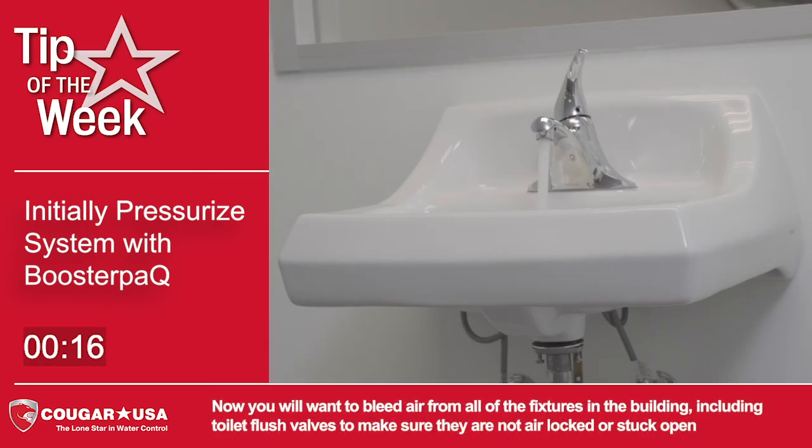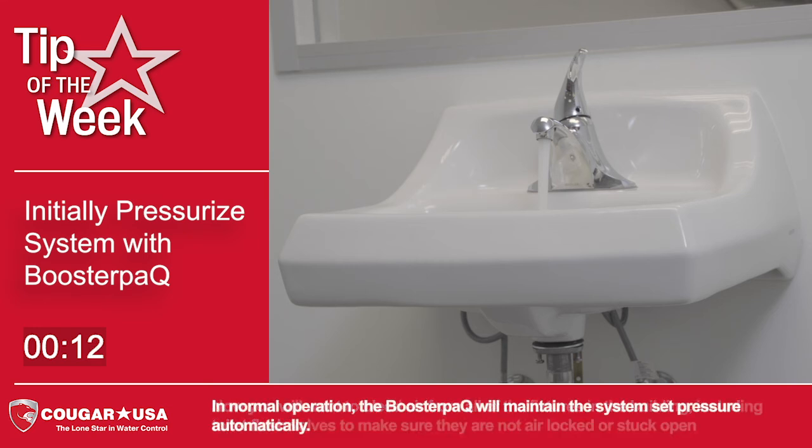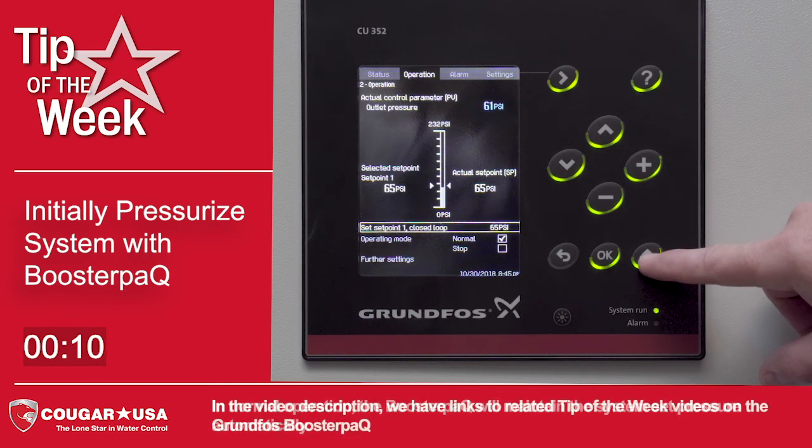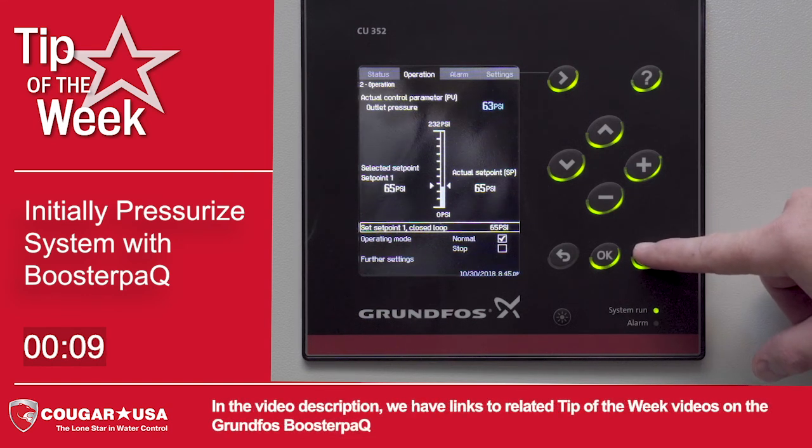Now you will want to bleed air from all of the fixtures in the building, including toilet flush valves, to make sure that they are not air locked or stuck open. In normal operation, the BoosterpaQ will maintain the system set pressure automatically. In the video description, we have links to related tip-of-the-week videos on the Grundfos BoosterpaQ.